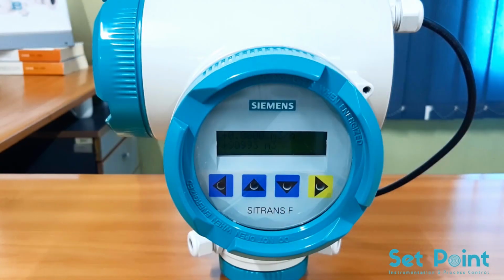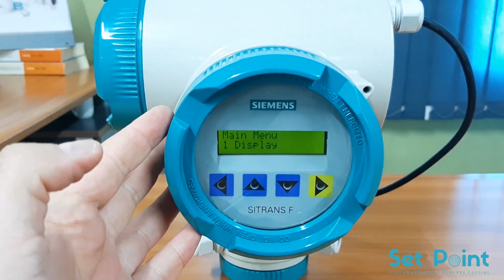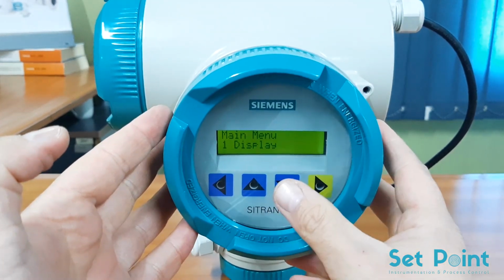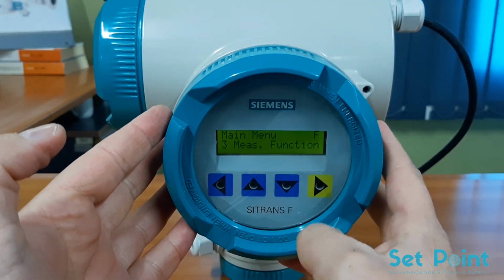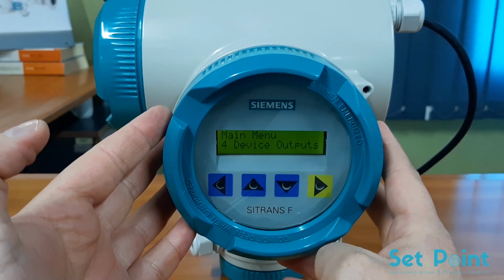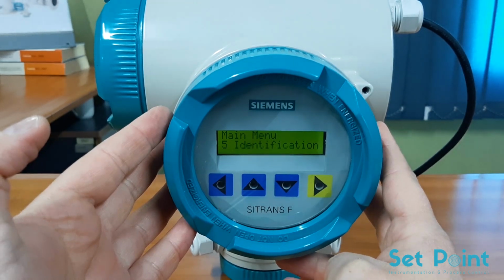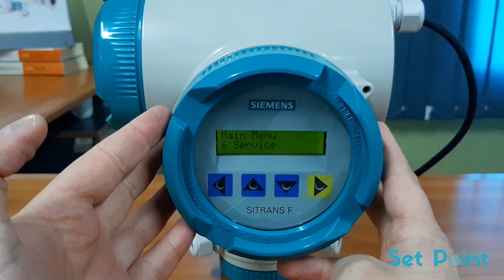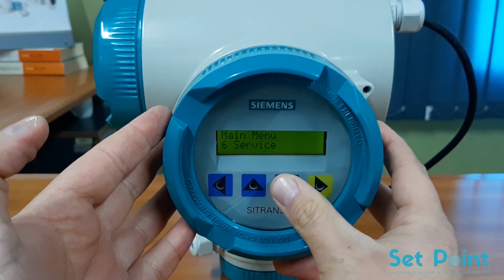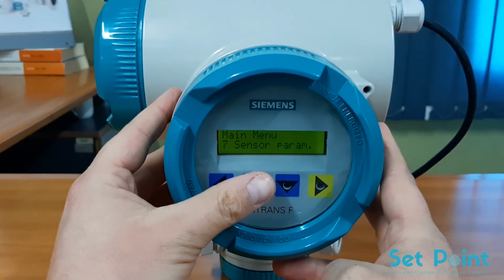The SITRANS FUS060 transmitter is operated with the optical keypad on the operating and display panel. These are operated by touching the appropriate fields on the glass panel with your fingertips. Here we have the seven main functions selected in the main menu. So we can navigate them by touching the enter or the forward key. We are presented with display, diagnostic, measurement functions, device outputs, identification, service, and sensor parameters. The individual functions and parameters for further groups are combined within these main groups.